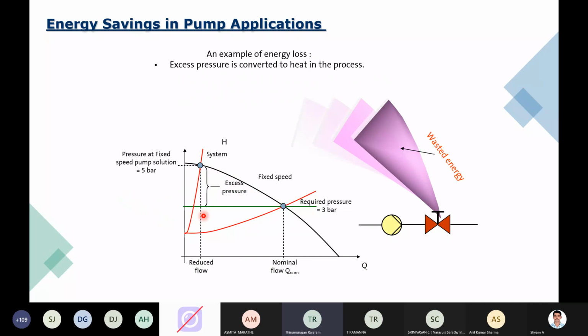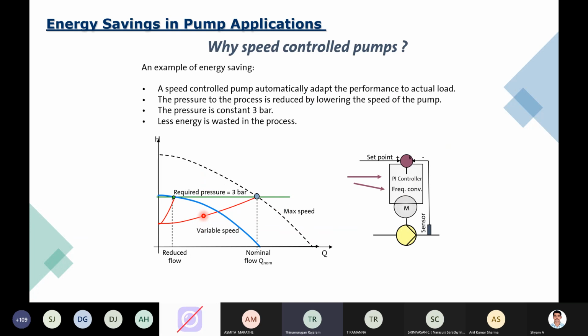But if you adopt that by removing a control valve and using a frequency drive, which operates based upon the input, here you can find you still maintain the same 3 bar pressure. There is no excess pressure. You can move from a nominal flow to a reduced flow very easily. So this will impact energy consumption a lot, and there will be a lot of potential for you to save energy in this aspect.